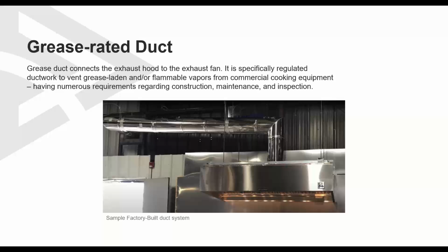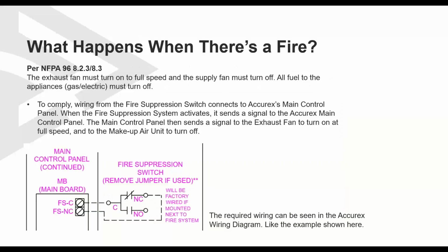There are grease-rated ducts. Grease ducts connect the exhaust hood to the exhaust fan. It is specifically regulated ductwork to vent grease-laden and/or flammable vapors from commercial cooking equipment, having numerous requirements regarding construction, maintenance, and inspection. And before I hand this off to Adam, the last slide here is what happens when there's a fire.